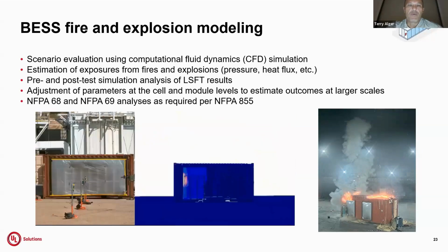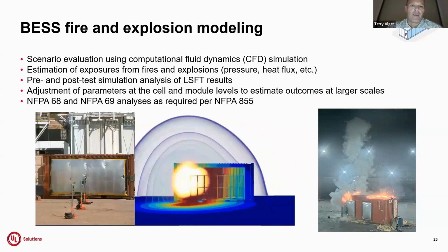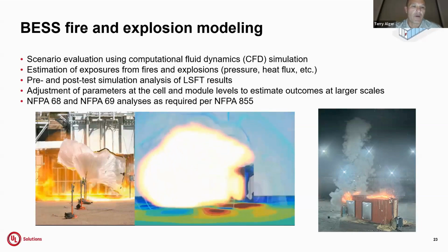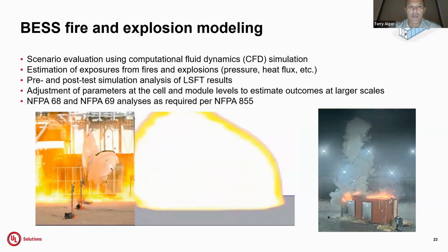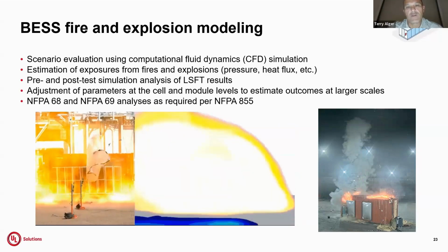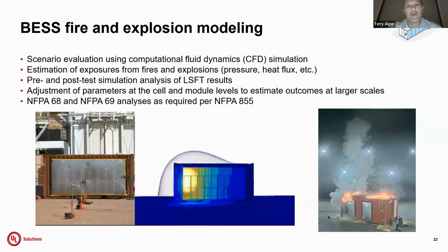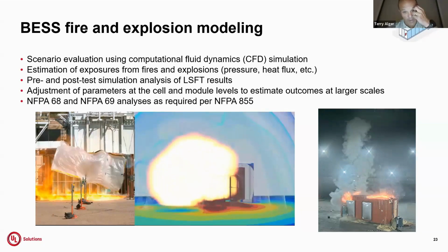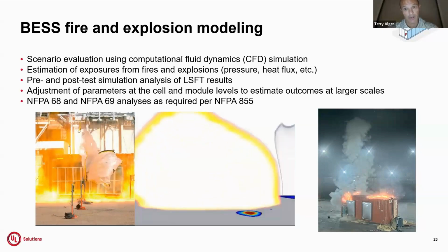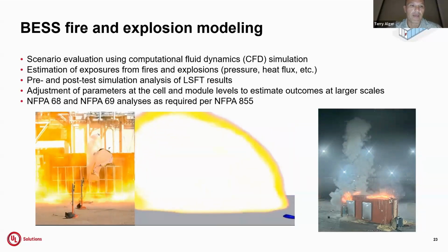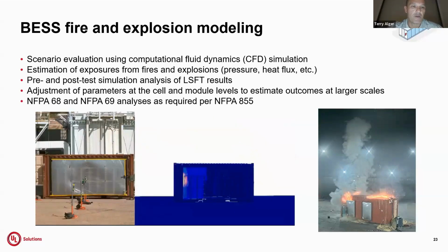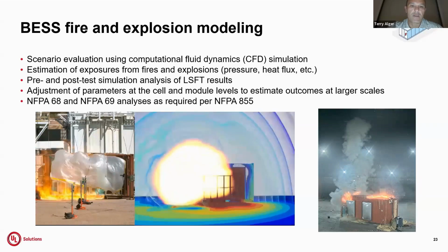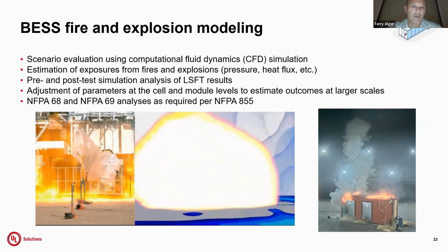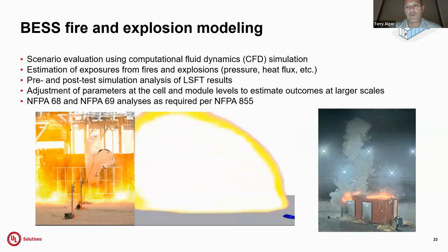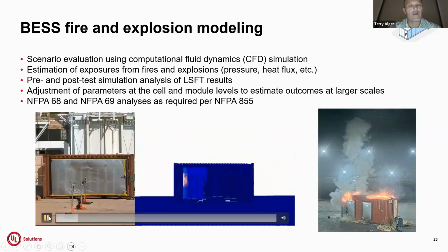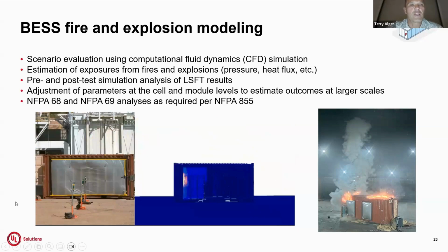The pre-test is very useful in that, in many cases, the code authorities that want to see these results want to make sure that the test that you're doing is often the worst case scenario. But rather than invest a considerable amount of money in multiple tests, oftentimes it's easier to simulate these tests and make sure that the condition we're running in is really going to be the worst case scenario, and provide that evidence to those AHJs.